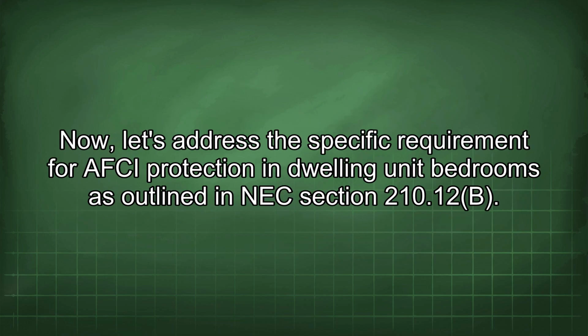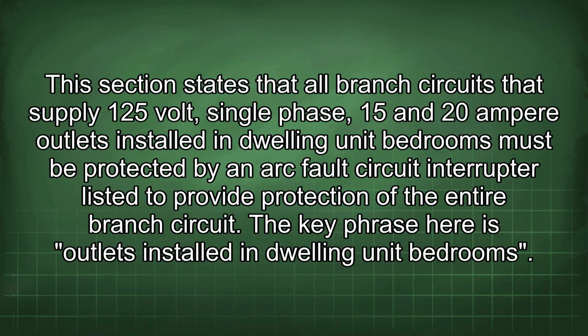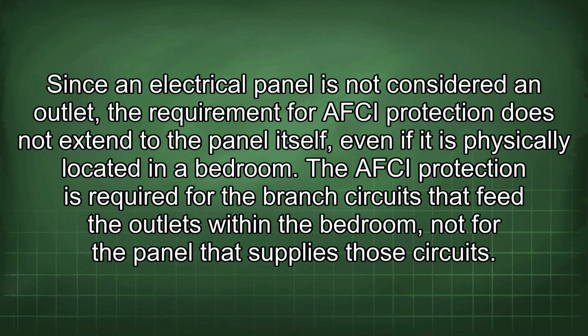Now let's address the specific requirement for AFCI protection in dwelling unit bedrooms as outlined in NEC section 210.12(B). This section states that all branch circuits that supply 125-volt, single-phase, 15 and 20 ampere outlets installed in dwelling unit bedrooms must be protected by an arc fault circuit interrupter listed to provide protection of the entire branch circuit. The key phrase here is outlets installed in dwelling unit bedrooms. Since an electrical panel is not considered an outlet, the requirement for AFCI protection does not extend to the panel itself, even if it is physically located in a bedroom.